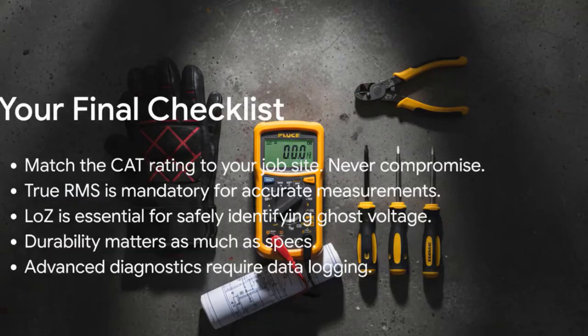So when you go to buy your next meter, here's your final checklist. One, match the CAT rating to your job - no excuses, no compromises. Two, it has to be True RMS, mandatory. Three, if you're doing commercial work, you need low Z. Four, don't forget about durability - a dead meter is a useless meter. And five, if you're the go-to troubleshooter, you're going to need data logging.